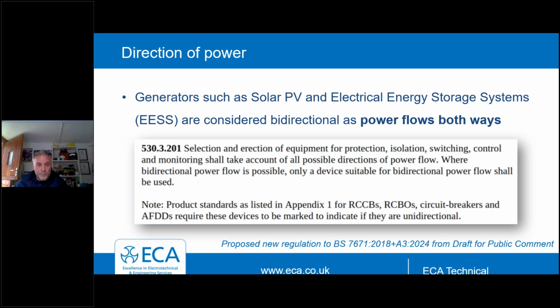But where we can possibly have problems with protective devices is where the voltage sits after what we call loss of mains. So if there's a loss of mains incident, either the protective device trips, so it opens, or you lose your connection to the grid. With a solar PV system, the loss of mains is triggered in that PV inverter. According to engineering requirements G98, which you might be familiar with, it can take half a second for that inverter to shut down completely to a safe level. Some older inverters will keep generating for 2.5 seconds. And what happens there is the voltage can sit on, should we say, the load side of the terminals. And that voltage presence has been highlighted by others as something that could cause a fault with protective devices.